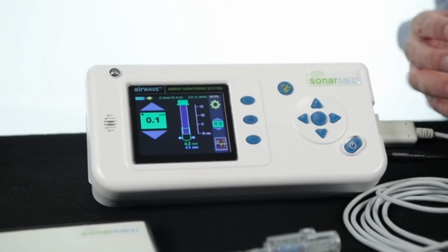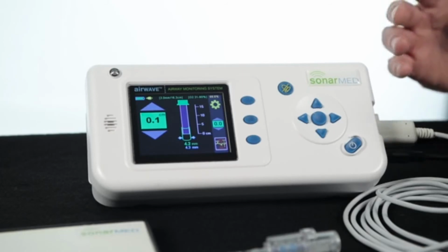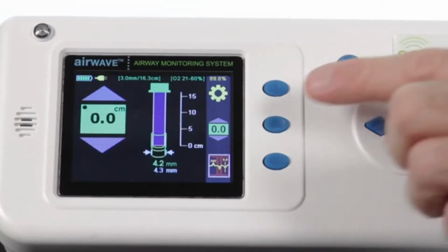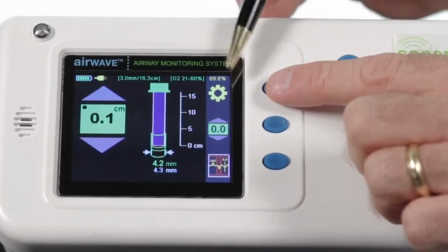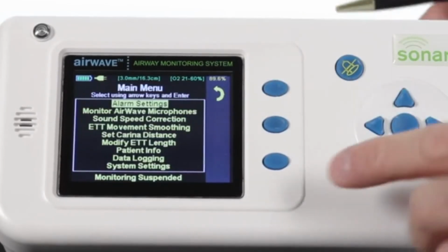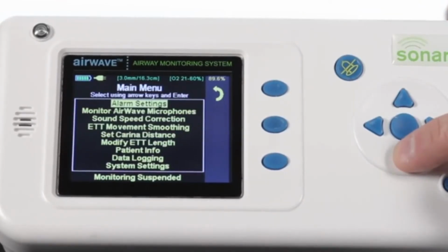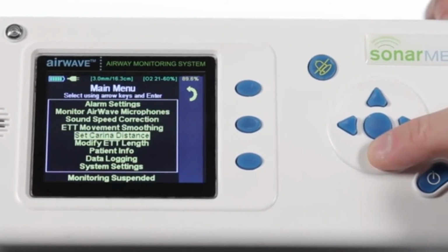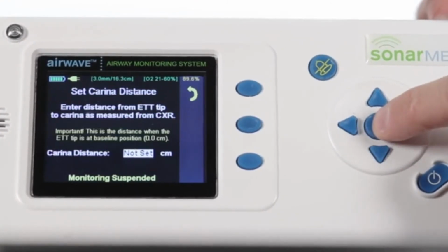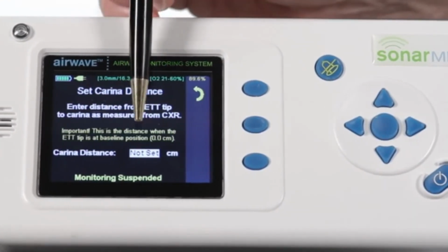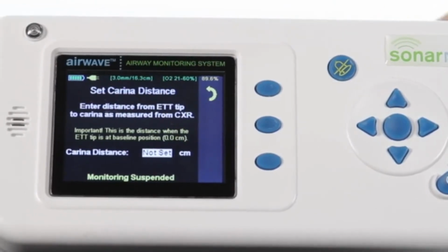So in this instance, we'll assume that the tip of the endotrach tube is ½ a centimeter away from the carina. The way we would enter that into the system is we would press the blue button to the right of the gear, and we would take the lower arrows down to set carina distance, and then hit the center to enter button. You can see right now it's telling us that the carina distance has not been set.